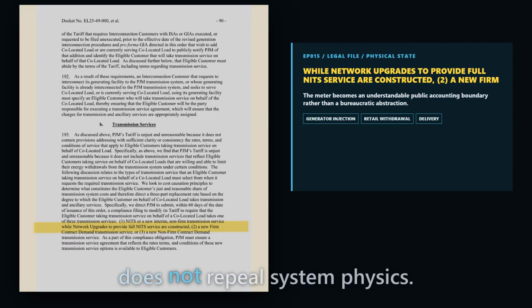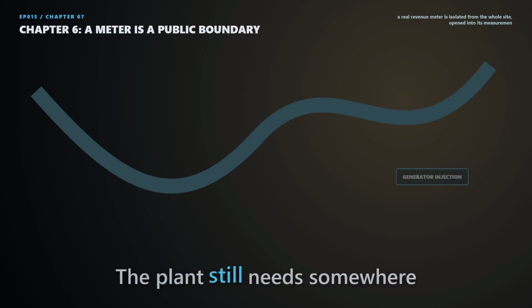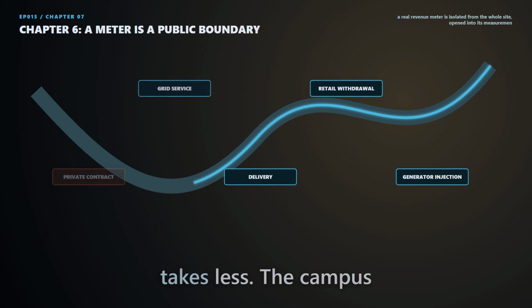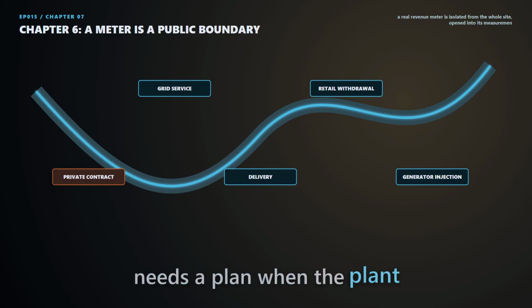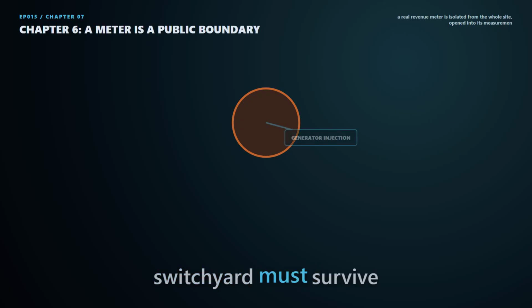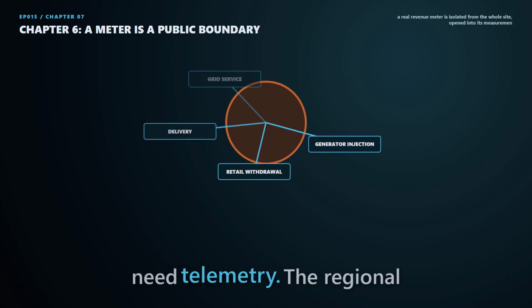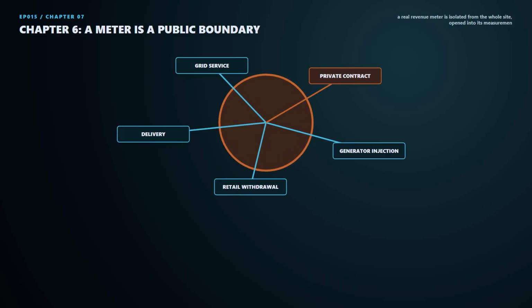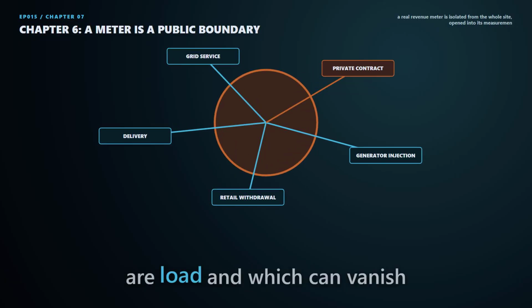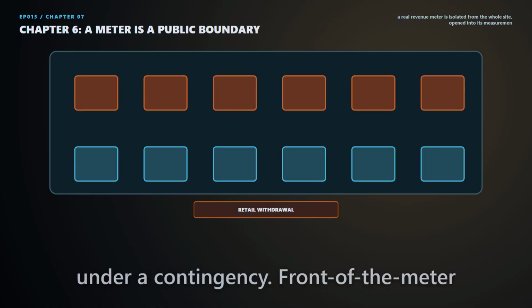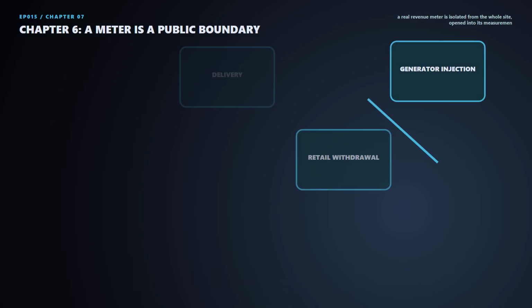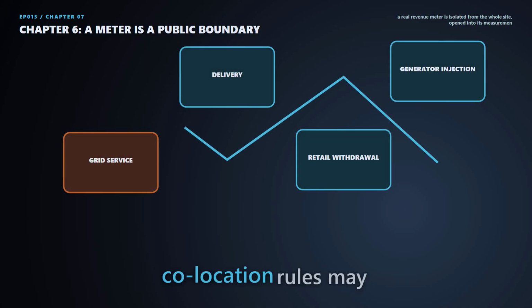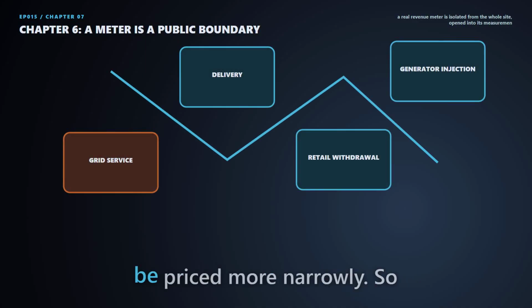But adjacency does not repeal system physics. The plant still needs somewhere to send power when the campus takes less. The campus needs a plan when the plant produces less. The switchyard must survive faults. Operators need telemetry. The regional market needs to know which megawatts are generation, which are load, and which can vanish under a contingency. Front-of-the-meter service makes those obligations explicit. Better co-location rules may later allow some of them to be priced more narrowly.